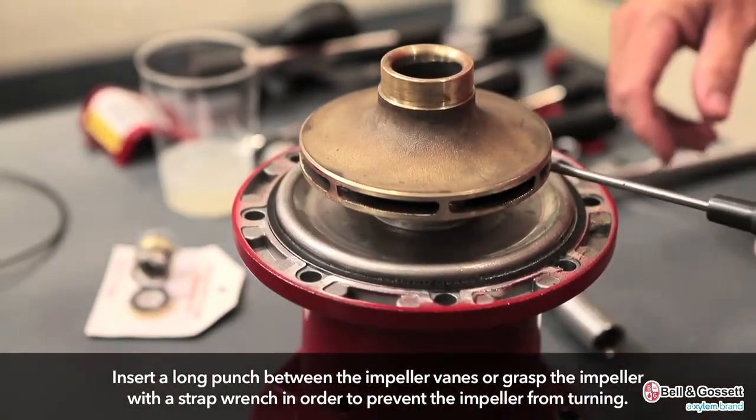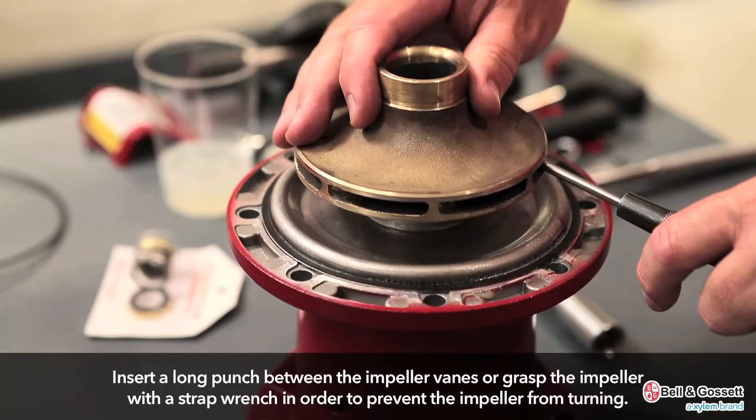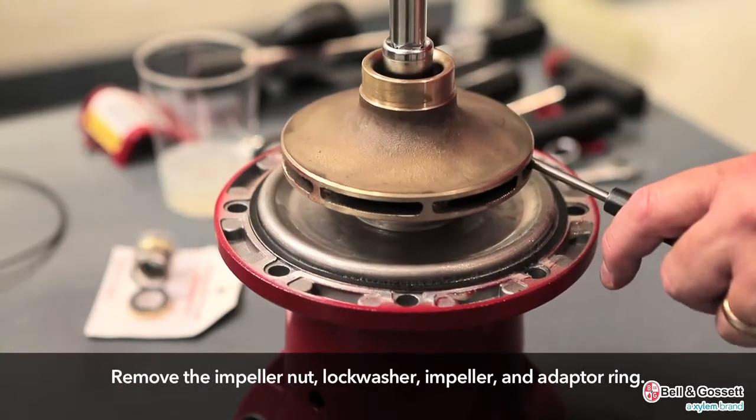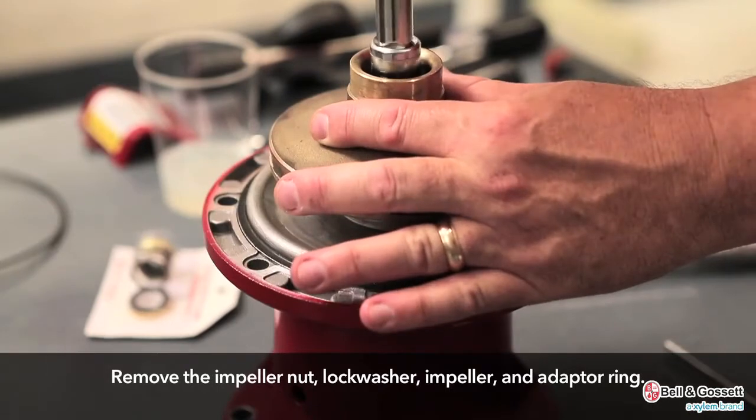Insert a long punch between the impeller vanes, or grasp the impeller with a strap wrench, in order to prevent the impeller from turning. Remove the impeller nut, lockwasher, impeller, and adapter ring.